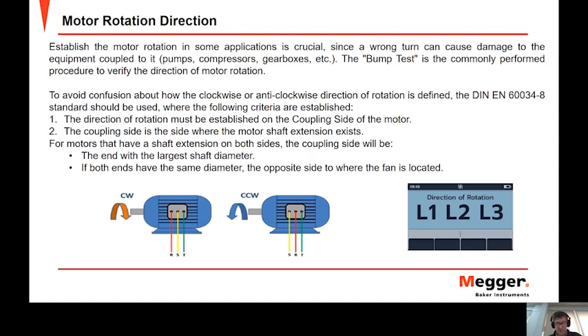So this is how we look at the motor rotation direction. We've checked the supply rotation first, and we have maybe L1, L2, L3. We then connect our 3 leads to our motor winding. We turn the shaft in the direction that we want the motor to turn in. And if we also get L1, L2, L3, then we know that the motor will start in that correct direction. And this can be crucial in some motor-driven applications, as incorrect rotation can cause damage to the driven equipment, such as pumps, compressors, gearboxes. The bump test is a commonly used test, but it will cause damage on some machines if it goes the wrong way, unless you decouple the motor from the load.